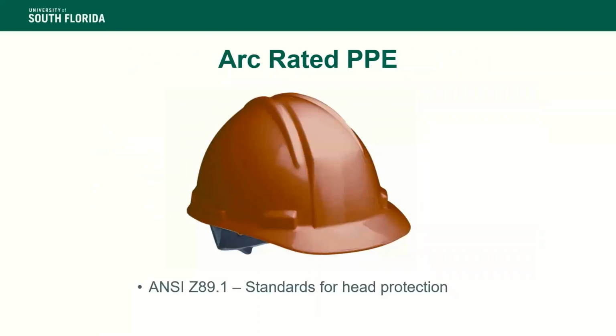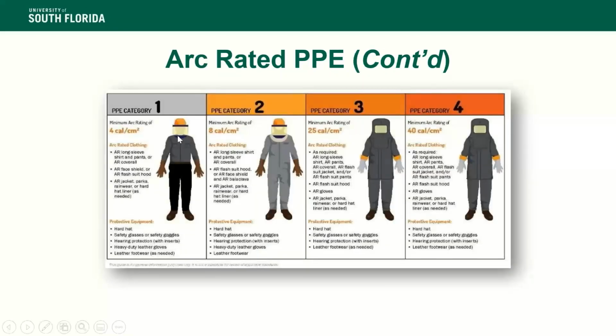Arc rated, again thinking about head protection, needs to be in compliance with ANSI Z89.1. Here's a nice pictogram that shows the different categories from category 1 to category 4. Category 1 is the minimum arc flash rating of 4 cal, then it goes up to 8, 25, 40. So the pictogram depicts different levels of PPE required for the individual to wear. This is a good chart to give you an indication of what you may need to follow to make sure you're in compliance with the proper PPE.